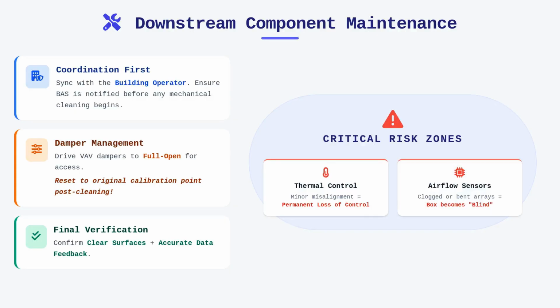Keep in mind that terminal units are specifically responsible for maintaining zone-specific thermal comfort, and even a minor misalignment of a damper resulting from our cleaning tools can cause a permanent loss of environmental control. Sensors for airflow are particularly vulnerable. They are often tiny, multi-port arrays that can be easily clogged by dust or bent during the cleaning process, rendering the box blind to the actual volume of air it is processing. Verify that these sensors are clear and calibrated before declaring the terminal unit operational, as a functional system requires both clean surfaces and accurate data feedback loops.